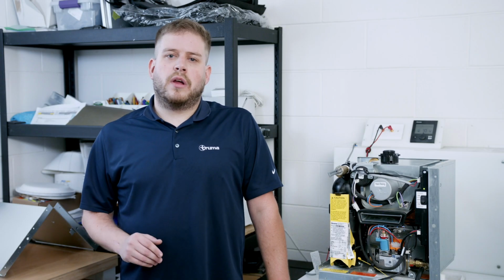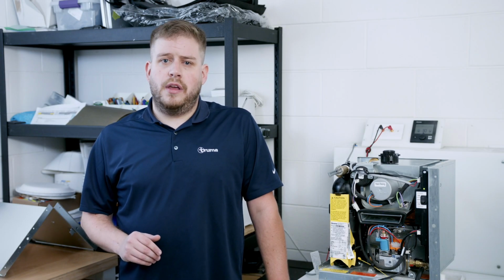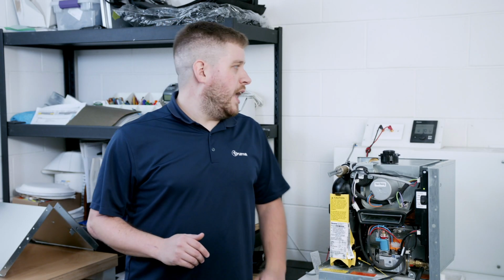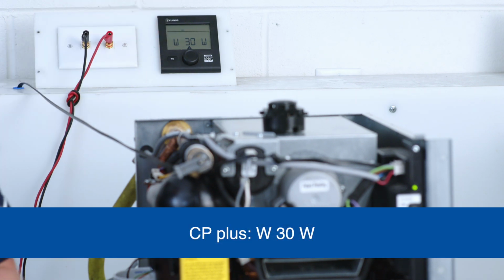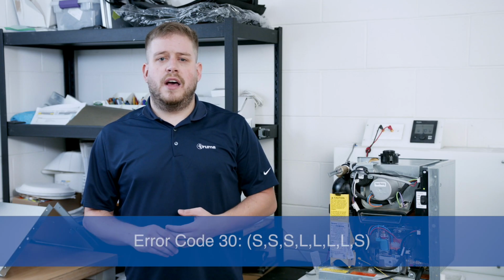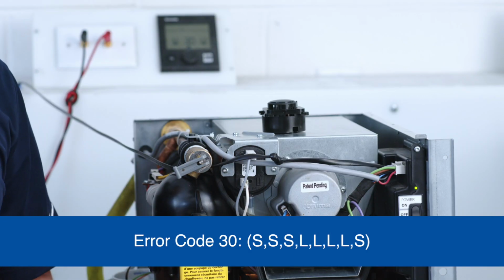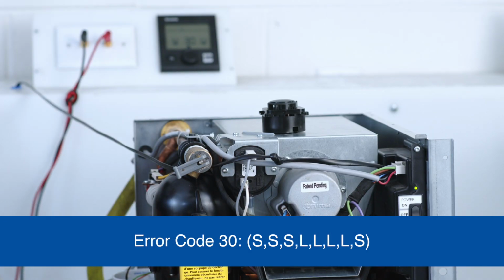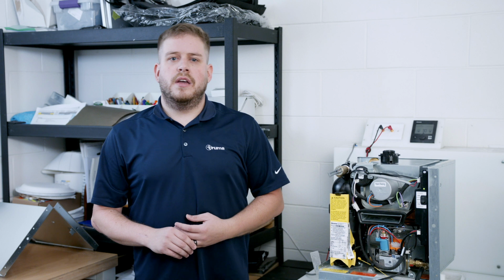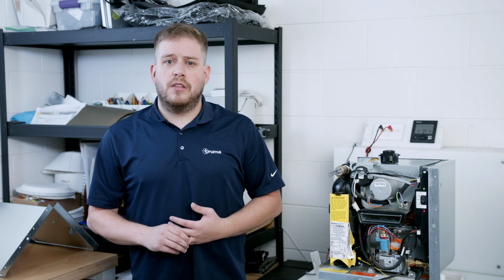The next error code we're going to be discussing is error code 30. On a CP Plus, that will be displayed as W30W. On the dial control, that will be displayed on the control board as 3 shorts, 4 longs, and 1 short flash for a total of 8. Error code 30 is a risk of freezing in the water heater.